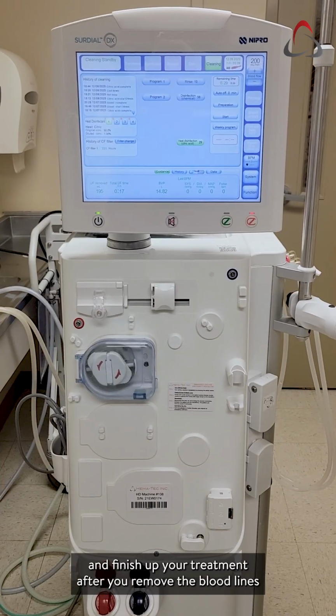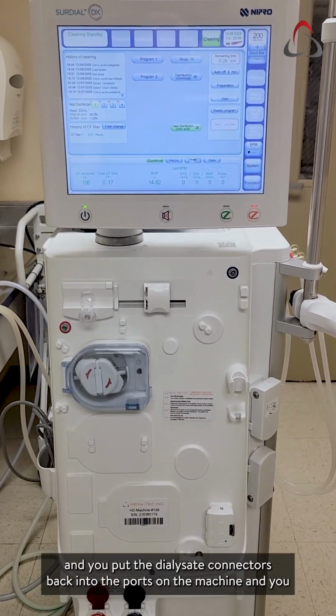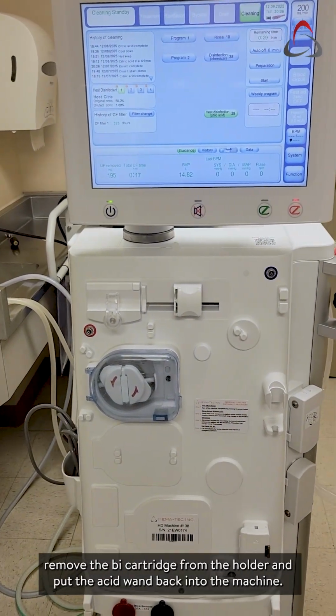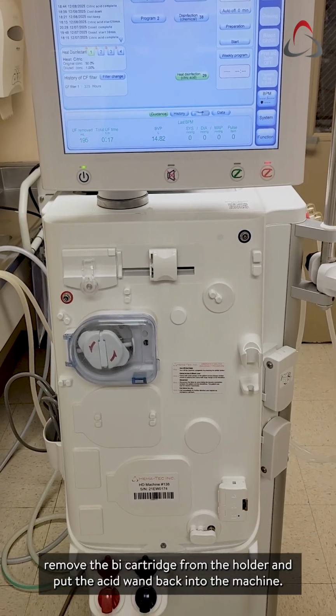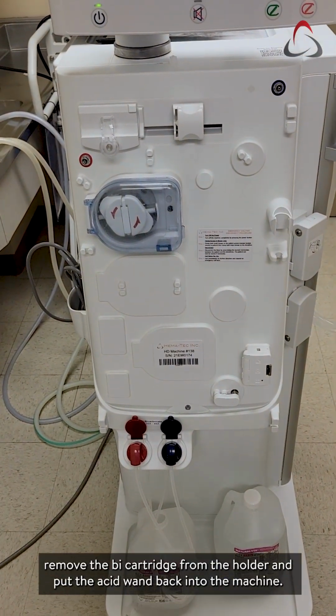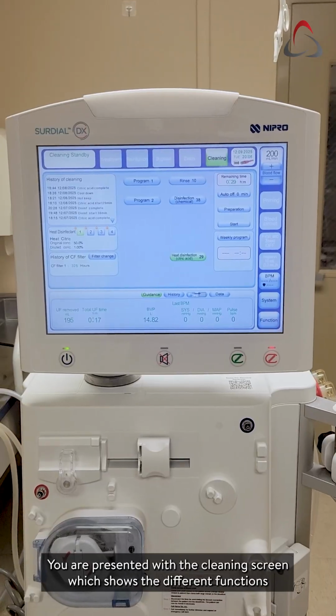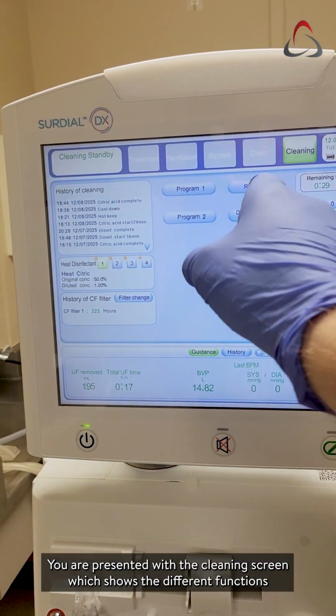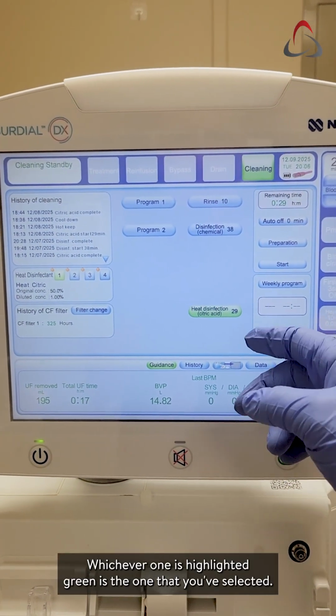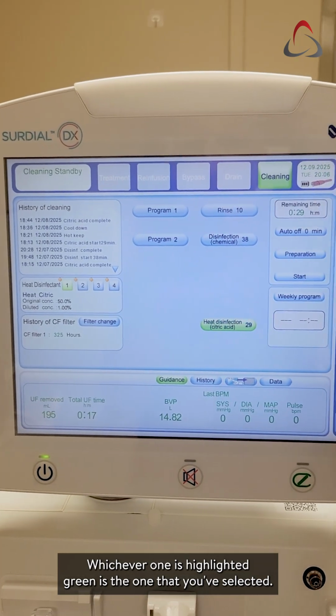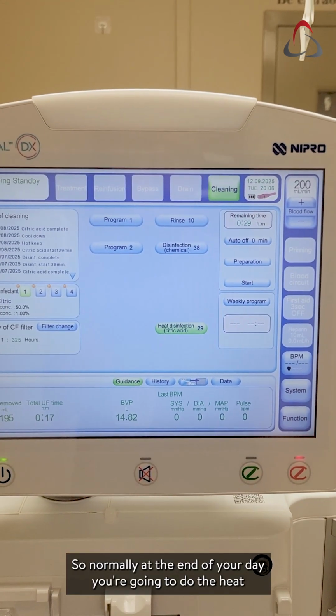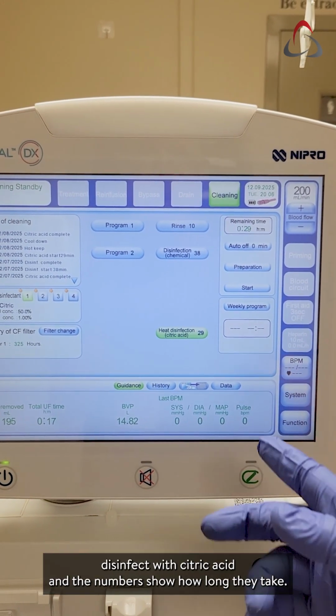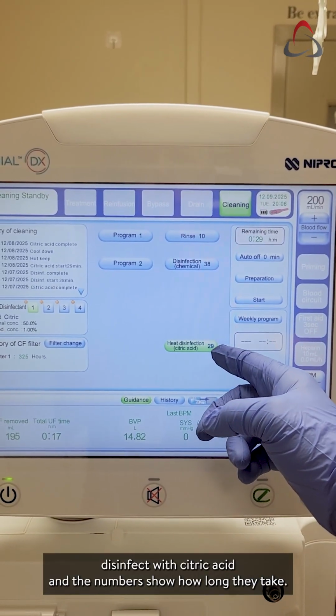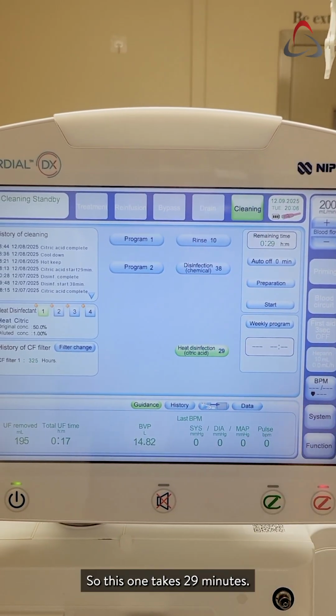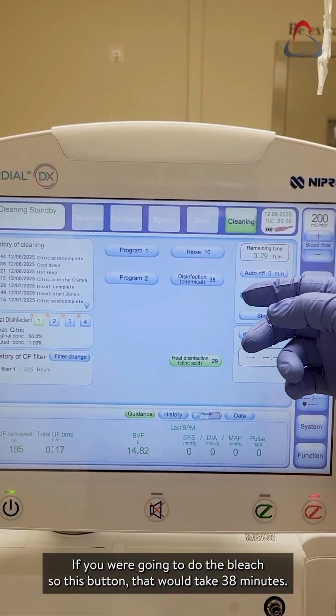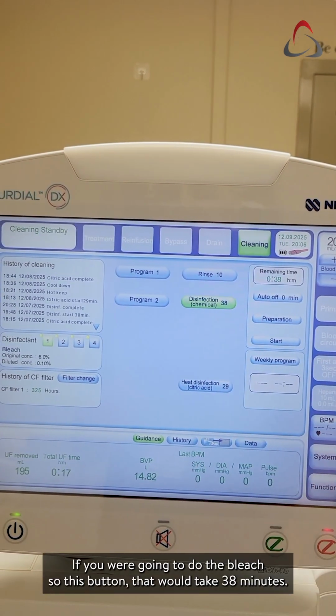After you remove the blood lines and put the dialysate connectors back into the ports on the machine, remove the bicarb cartridge from the holder and put the acid wand back into the machine, you are presented with the cleaning screen, which shows the different functions for cleaning. Whichever one is highlighted green is the one you've selected. Normally at the end of your day, you're going to do the heat disinfect with citric acid, and the numbers show how long they take. This one takes 29 minutes. If you were going to do the bleach, this button, that would take 38 minutes.